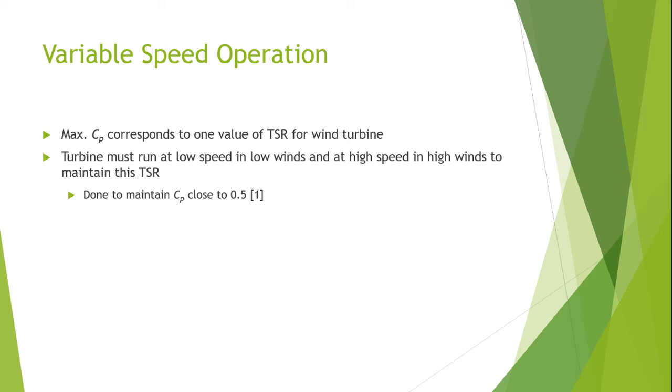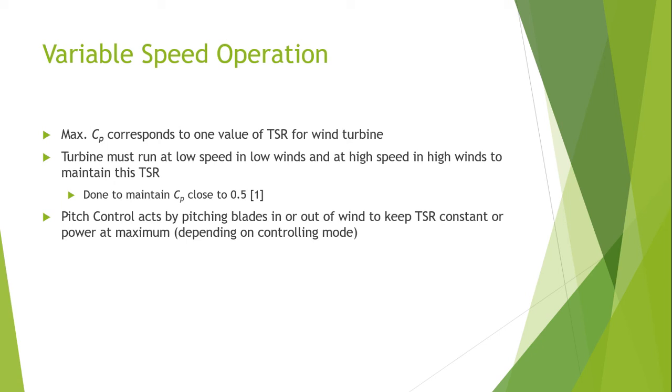One must ensure to maintain a constant TSR ratio. This is done to maintain the Cp, that's the rotor efficiency, which must be maintained close to 0.5.